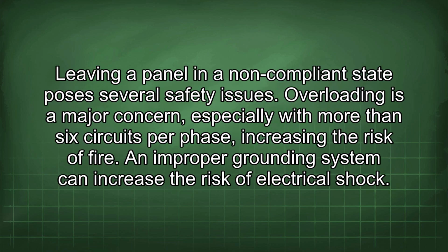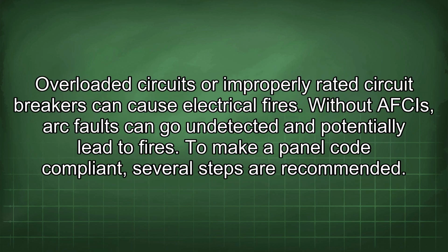Leaving a panel in a non-compliant state poses several safety issues. Overloading is a major concern, especially with more than 6 circuits per phase, increasing the risk of fire. An improper grounding system can increase the risk of electrical shock. Overloaded circuits or improperly rated circuit breakers can cause electrical fires. Without AFCIs, arc faults can go undetected and potentially lead to fires.